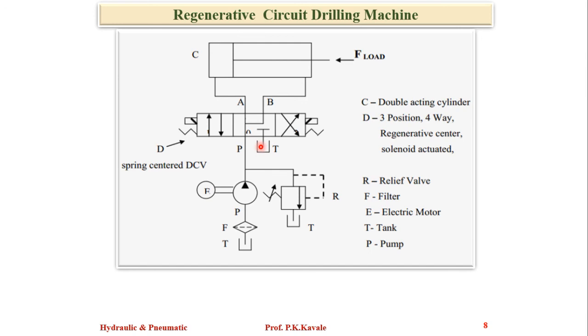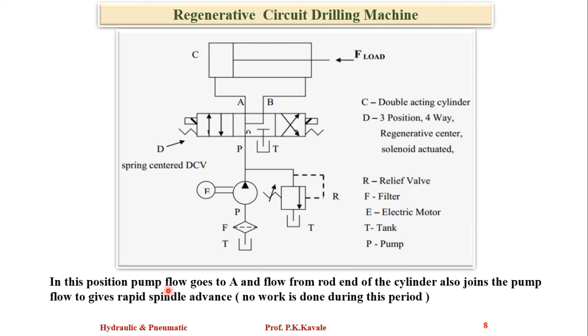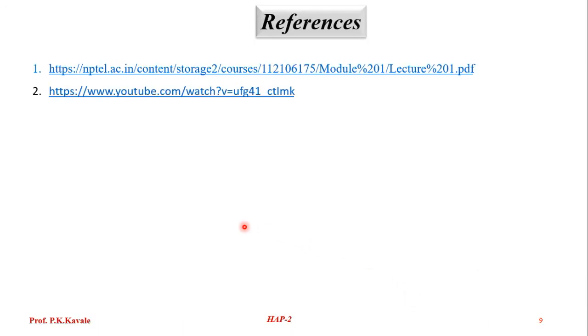This is exactly the application of the regenerative circuit. In this position, pump flow goes to port A, and flow from the rod side of the cylinder also joins the pump flow to give rapid spindle advance. No work is done during this period. When idle, the spindle should return to its normal condition.